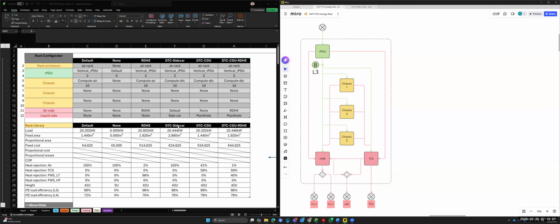We also have a direct-to-chip sidecar, basically where you have a rack sitting alongside the IT rack. In that case, the heat's rejected from the chassis two ways: a proportion on the liquid side, which is then cooled by the sidecar sitting in the TCS location, and some of the heat is rejected to the air side.